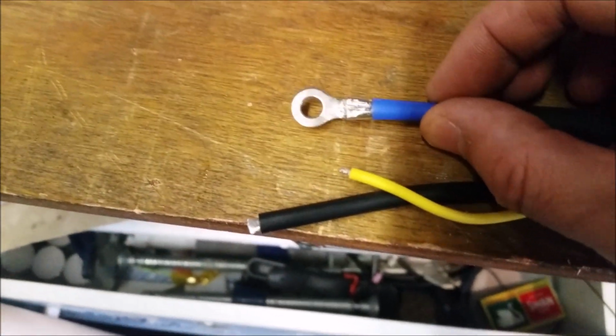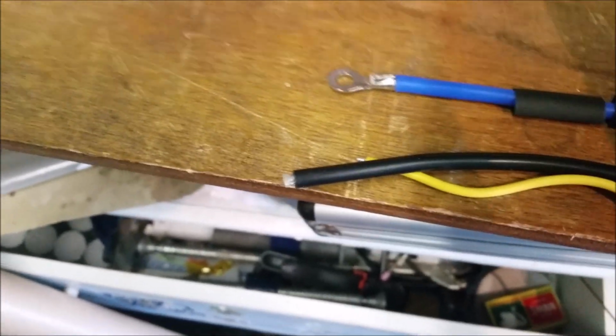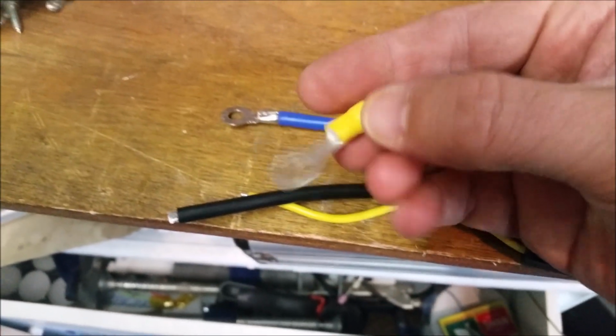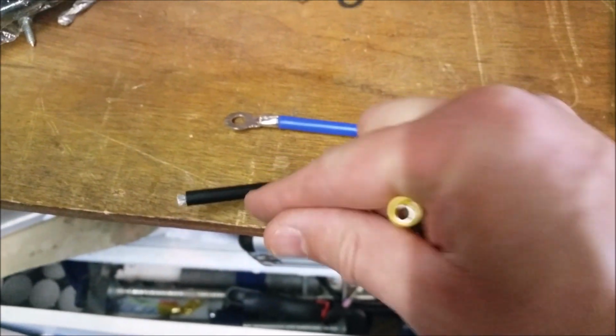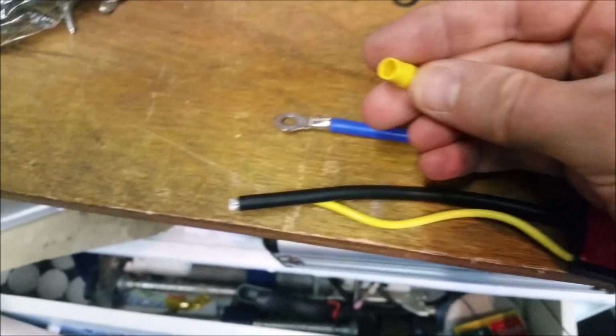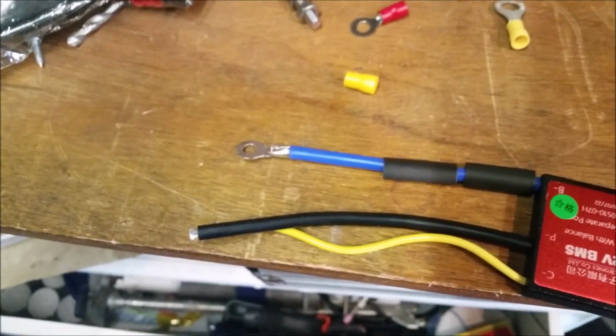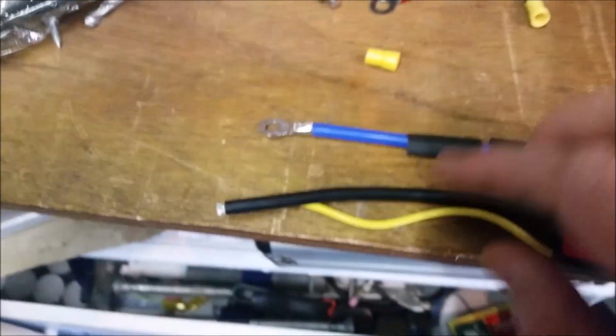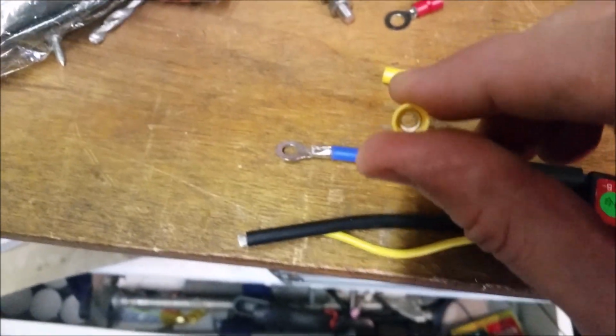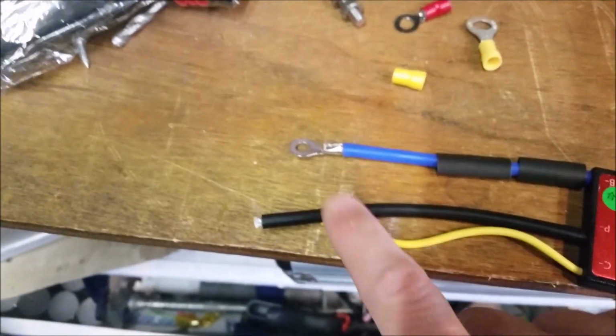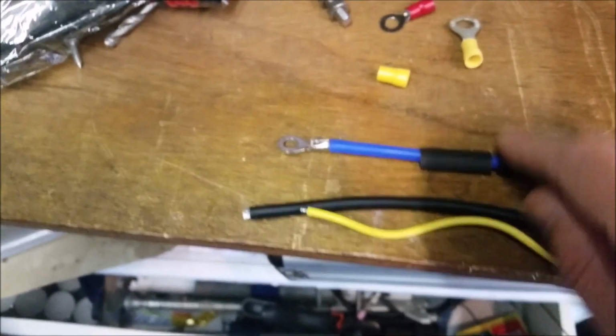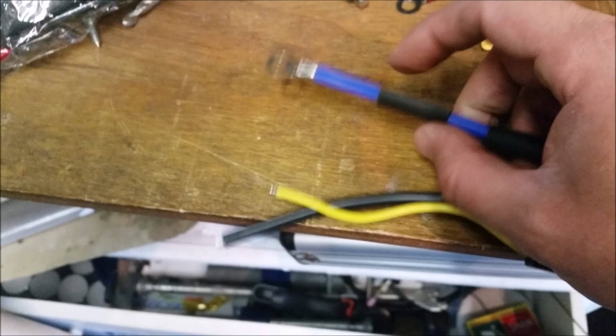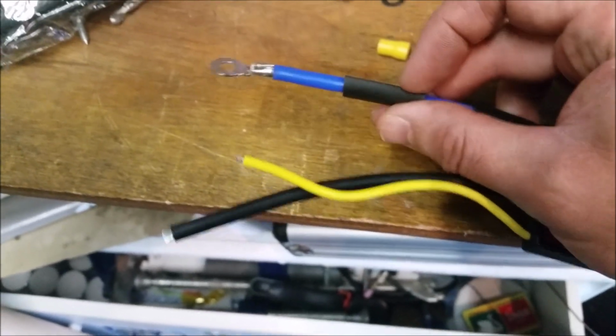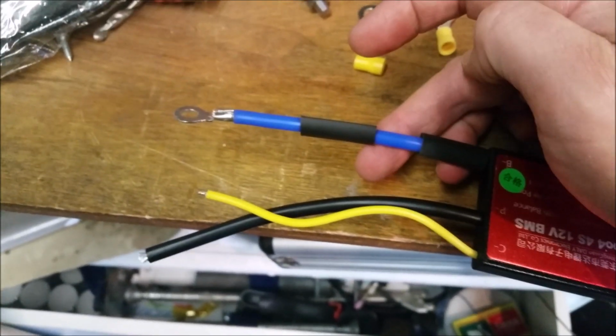Right, first engineering challenge: this wire is 10 gauge, these crimps are 12 gauge, so I have to take off the plastic sleeve and open up the ferrule inside to allow me to get the wire on. Then, just to give it some insulation, I'm going to whack two layers of heat shrink over there.